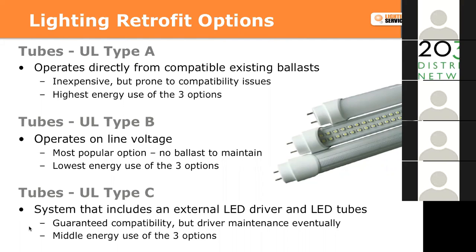You've all probably seen this in some form in your facilities, but it operates off of either an existing electronic ballast, line voltage, or an externally tied together system, which would be an LED driver. We find the most popular is the center one, the UL Type B, which is line voltage. Most people want to get the ballast out of their facilities, but if that's a concern, UL Type C would probably be your next best option.